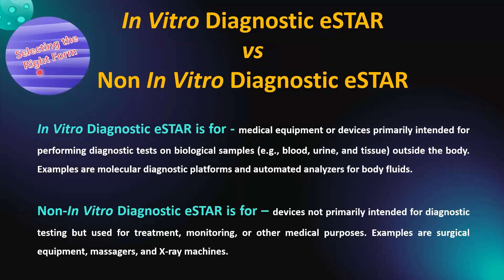To initiate the process, selection of the right form is very important. The in-vitro diagnostic eStar PDF form is for medical equipment or devices primarily intended for performing diagnostic tests on biological samples like blood, urine, and tissue outside the body. Examples are molecular diagnostic platforms and automated analyzers for body fluids. The non-in-vitro diagnostic eStar is for devices not primarily intended for diagnostic testing but used for treatment, monitoring, or other medical purposes. Examples are surgical equipment, massagers, and X-ray machines.